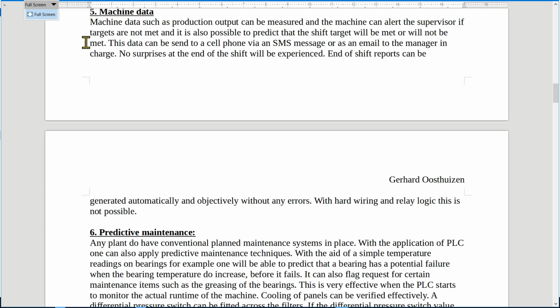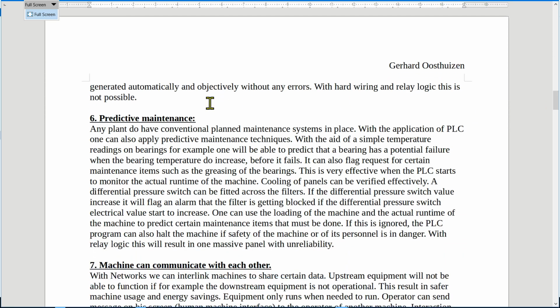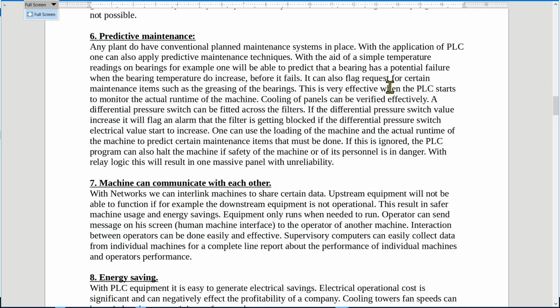Now, this data can even be sent to a cell phone via SMS message or as an email to the manager in charge. And you don't have to get to the end of the shift before you realize that there's a serious challenge, because then it's too late. For example, an end of shift report can be generated automatically, and this report is objective. The PLC will not tweak the figures, it will actually give you the real objective data. Now again, with hardwiring and relay logic, this is not possible.